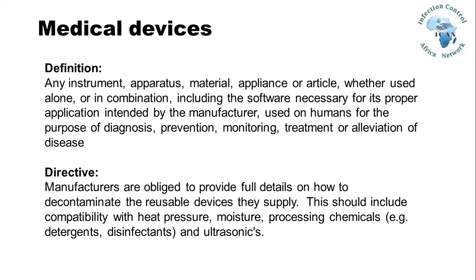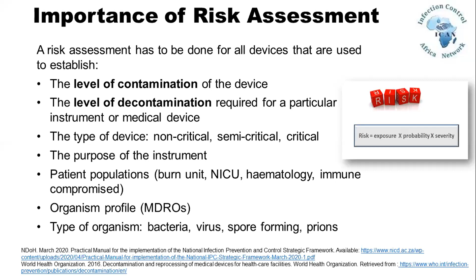So what happens now? We know that a risk assessment has to be done for all devices that are used to establish the level of contamination, the level of decontamination required for that instrument, and the type of device. Is it non-critical, semi-critical, or critical? And we'll speak more of that now. The purpose of the instrument, where it gets used, and on what type of patients. Know the multi-drug resistant organism profile of your institution, and also what organism you are dealing with: a bacteria, a virus, a spore-forming organism, or a prion.